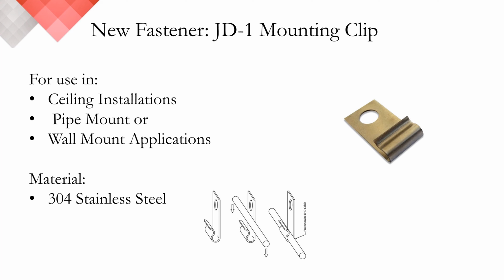The JD1 clip was developed to provide installers an easier method of supporting and installing linear heat detection. Most, if not all, the supports offered are closed-loop format. These have been effective accessories for a great many years, but are sometimes problematic when making quick repairs. To do so would typically require the removal of the clip, and then the detector, and then reinstalling the clip along with the detector. A lot of time and effort is spent in between. The JD1 design resembles a J slot with an open top and a slightly narrowed opening. The open top allows for a quick installation and removal of the detector without the need to remove or replace the clip, saving you both time and money.